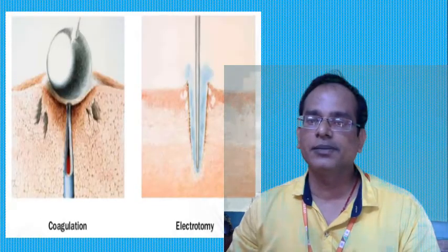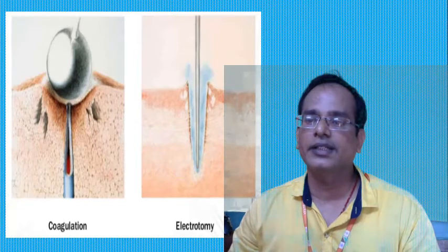So here is the working principle of electrosurgery. Radio frequency starts at 3 kilohertz and extends through 300 gigahertz. At this frequency, neither muscle nor neural cells are depolarized. RF electrosurgery requires creation of an electrical circuit that includes the patient, the ESU, and connecting wires. The ESU converts electrical energy drawn from the mains supply to high frequency current. That is the main function of the ESU.